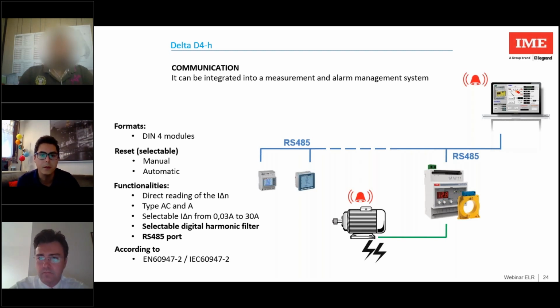For example, as we say, for the TN system, you don't have to use it, or better, you use it only for backup or for only certain types of load. You don't have to use the ELR because a loss of insulation between one conductor and the neutral, for example, is a short circuit. So you have to use a thermal breaker.